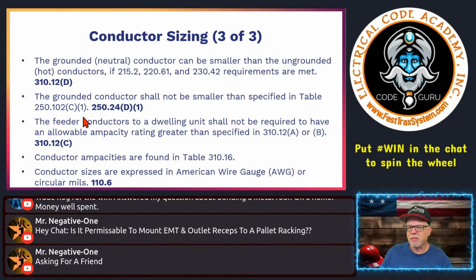Okay. Let's see here. Next, it says the grounded conductor shall not be smaller than specified in table 250.102(C)(1) as referenced in 250.24(D)(1). You heard me reference that a minute ago. Okay. And then it says the feeder conductors to a dwelling unit shall not be required to have an allowable ampacity greater than specified in 310.12(A) or (B). This is just saying, look, if you're running that feeder to an individual dwelling unit, you don't have to have it be larger than what the calculation requirement would have been in 310.12.